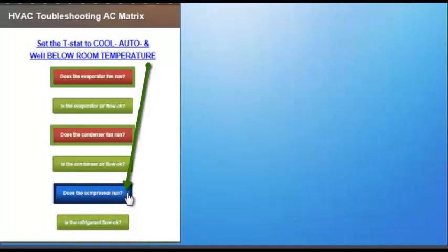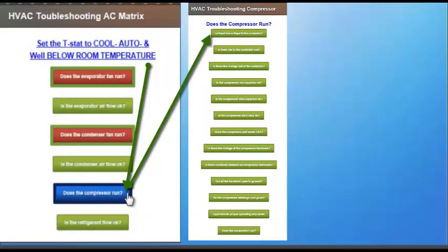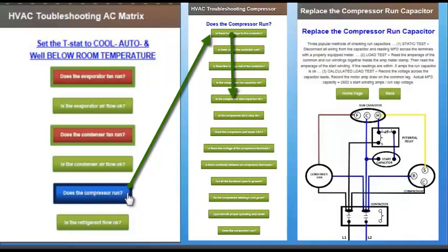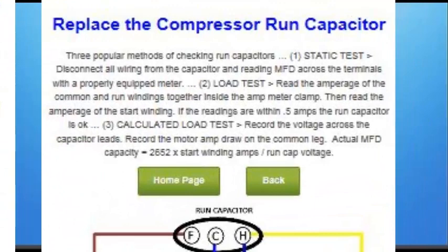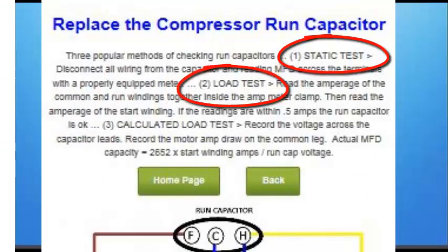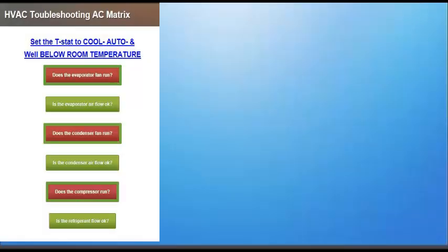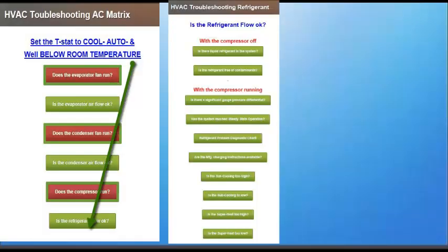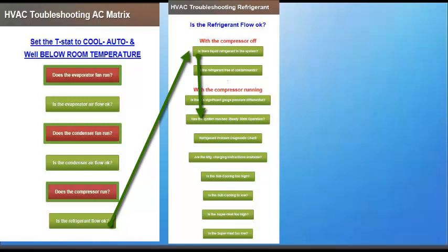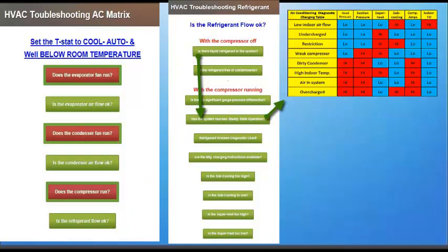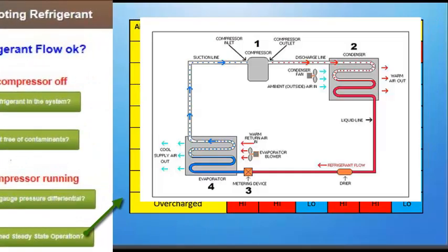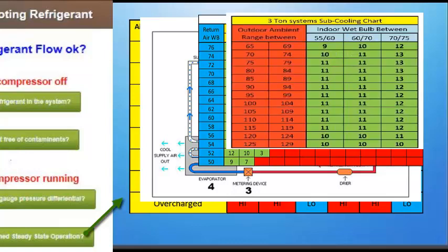Process can define the quickest and most efficient path to when a technician should suspect a problem with a capacitor. Once there, however, the technician must know the procedure for testing a capacitor. The matrix provides technicians with three different procedures for testing run capacitors: a static test, an operating load test, and a calculated load test. In another example, process can define the quickest and most efficient path to when a technician should suspect a problem with refrigerant flow. Once there, the technician must know the procedures for evaluating and correcting refrigerant flow and refrigerant charge problems. The matrix provides technicians with a refrigerant problem diagnostic chart, a refrigerant cycle diagram, and generic charging charts as aids in this transition between process and procedure.